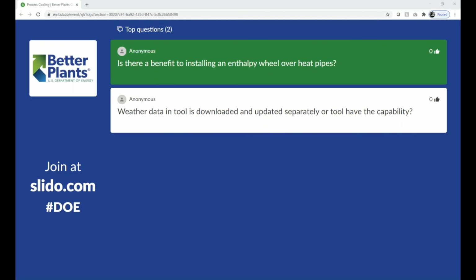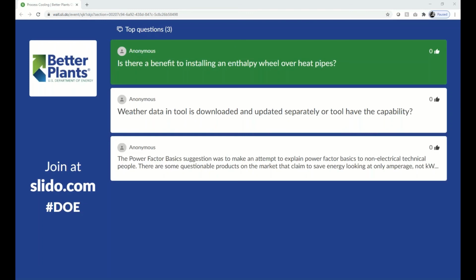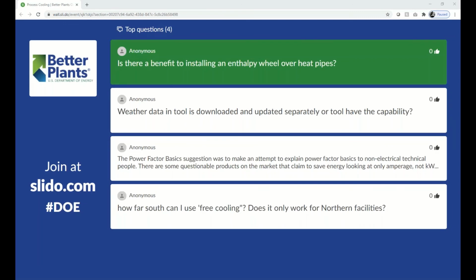But for enthalpy wheels, the intake airstream and the exhaust airstream will go through the same channels over time. So, if you are concerned about air quality, enthalpy wheels might give you some cross-contamination for your air. But for heat pipes, that problem does not exist, because the intake airstream and exhaust airstream never go through the same channel. So the cross-contamination for heat pipe use is very, very little. So yeah, if you want high efficiency and your application does not really have a high requirement on air quality, you can use enthalpy wheels. Otherwise, you can choose heat pipes.